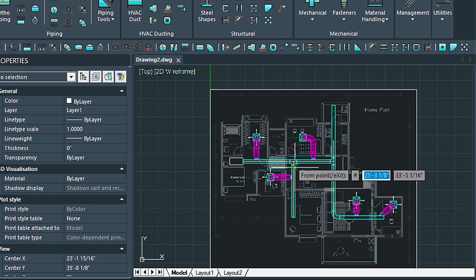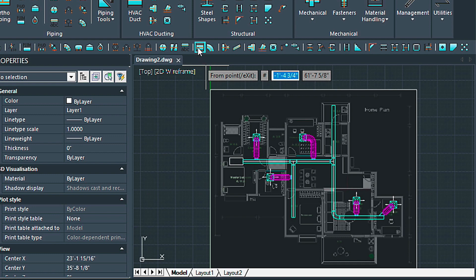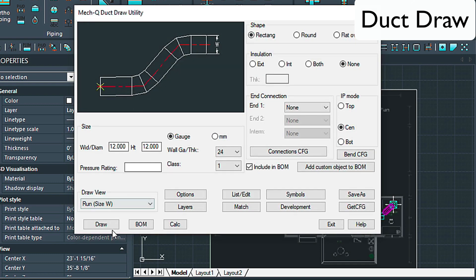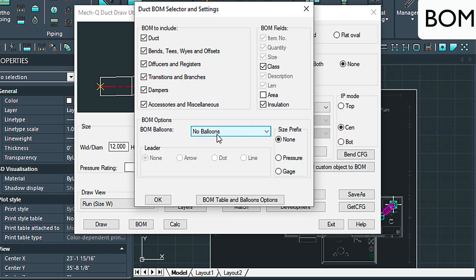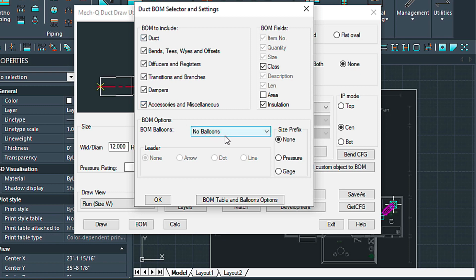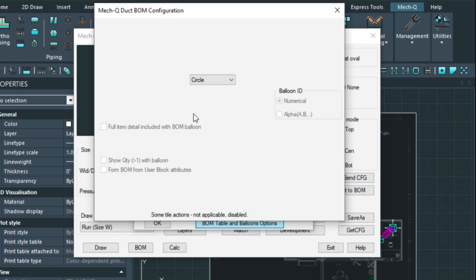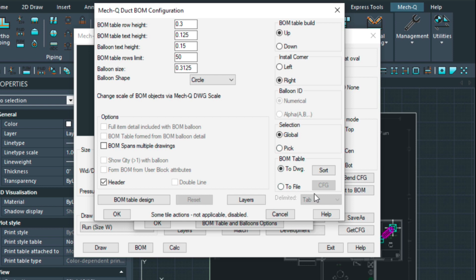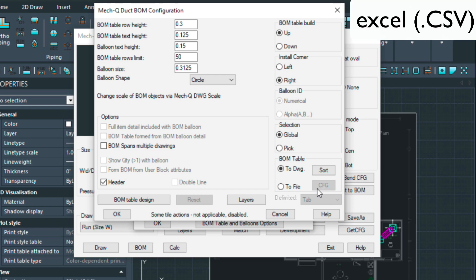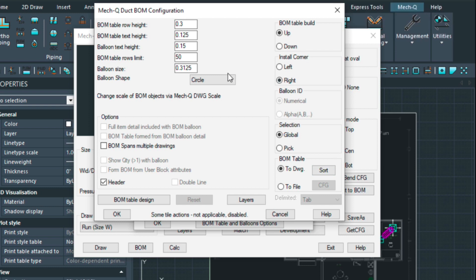Now that we have all this drawn in, let me show you how to create the bill of materials. Come over to the main duct utility and choose BOM. Here we can choose what we want to include. I've got no balloons selected to keep the video short, but if that's turned on it will prompt you for each item. In the configuration menu you can tell the bill of materials to be sent to the drawing file or to a file — that will allow you to open it in Excel as long as it's a CSV file; you have to rename it to CSV. I have a video about that as well.